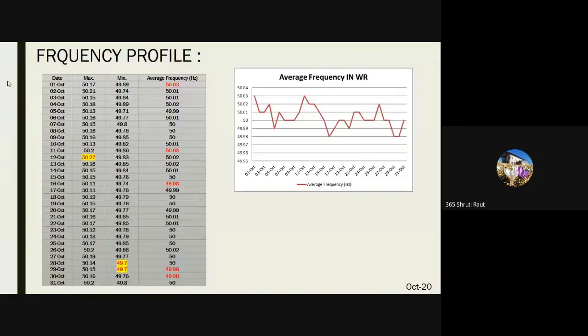Now we will see the frequency profile. Here we can see the average frequency graph at the RHS side. Maximum frequency observed for this month at 12 October, that is 50.27 Hz, and minimum frequency observed two times, that is 28 October and 29 October, 49.7 Hz. So, system frequency remained in the IEGC band. IEGC stands for Indian Electricity Grid Code. That is, this band indicates that good frequency is 49.9 to 50.05 Hz or 81.87 of the time in this month. Average frequency was 50 Hz and frequency deviation index was 0.18.